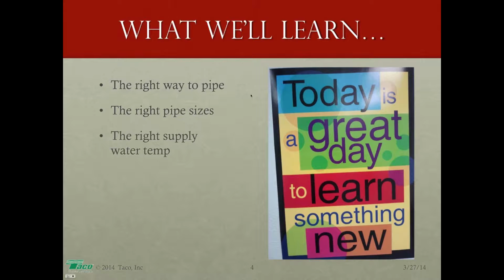We're also going to discuss how to select the right supply water temperature. What temperature do we need to supply to the system, but also what temperature do we need the boiler to fire to? They're not necessarily the same things, and that can create some issues. And we're finally going to wrap up with a quick review and discussion on the benefit of hydraulic separators and buffer tanks, what they do, what they don't do, and why you might want to consider them in your piping arrangement. There's two very good reasons for considering the use of these things in your piping arrangements, and we'll go over both of those.